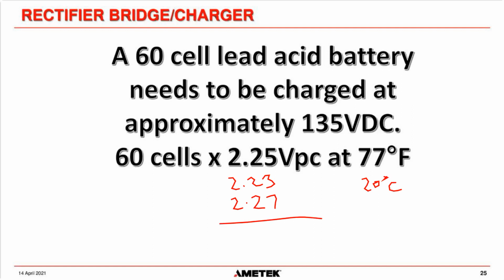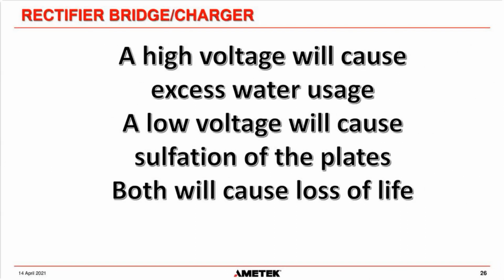You need to make sure that the appropriate charge voltage is given to your batteries, because if you overcharge them, they can go into thermal runaway, and if you undercharge them, they can lose life rapidly because the plates will sulfate. A high voltage will cause excess water usage in wet cells or thermal runaway in valve-regulated cells, and a low voltage will cause sulfation of the plates. Both cause a loss of life in the battery.